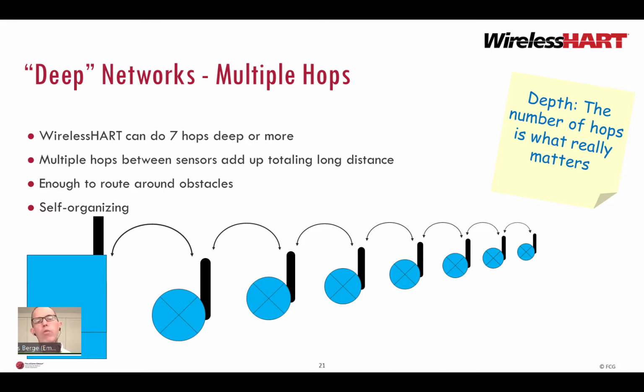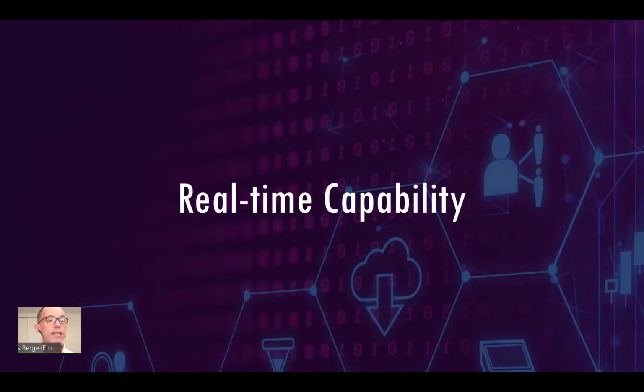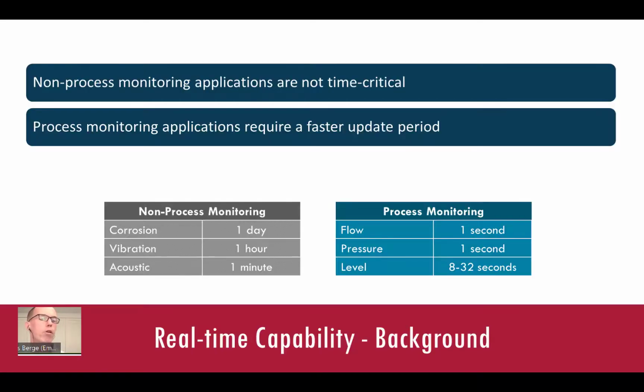So when comparing wireless sensor network technologies, ask not what is the maximum range from gateway to sensor. Instead, ask what is the depth, the maximum number of hops in one communication path. WirelessHART can do 7 hops deep or more. This capability allows WirelessHART to reach sensors deeper inside the plant units than other technologies can. As a result, the multi-hop capability gives WirelessHART the longest effective range and greatest coverage in a plant.